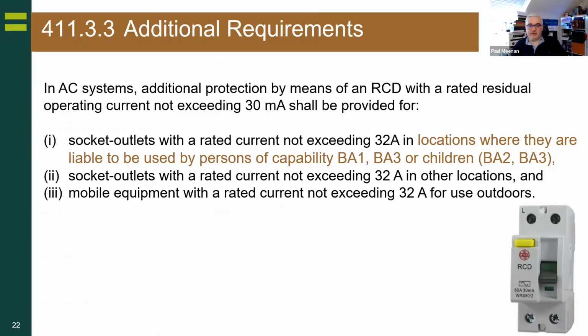411.3.3 in the additional requirements section. So RCDs have been a thing since the late 90s. They were introduced in the 16th edition, and they're a good thing. They're an additional protection, or what they used to be called supplementary. In the last edition, everything went up to 32 amps. So anything up to 32 amps, a circuit breaker or a device, we would apply RCDs unless you wanted to risk...